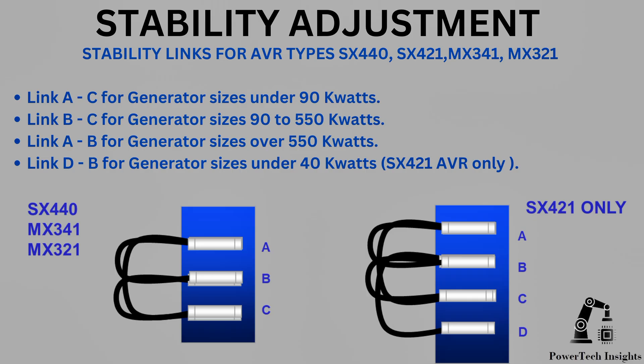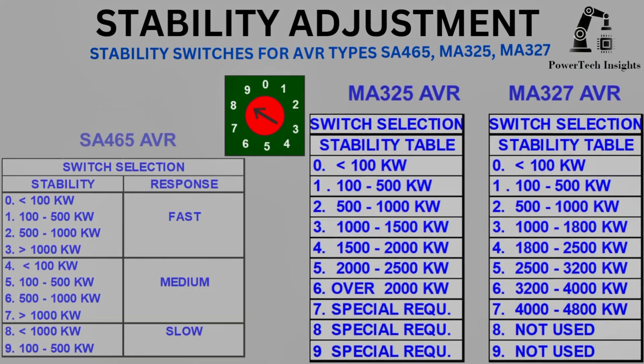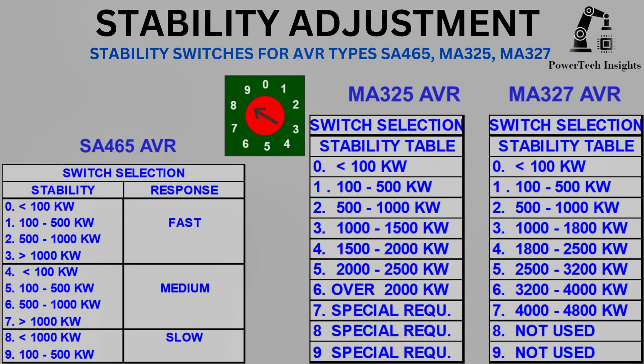Link D to B for generator sizes under 40 kilowatts — SX421 AVR only. Stability switches for AVR types SA465, MA325, and MA327 can be found in the corresponding tables.